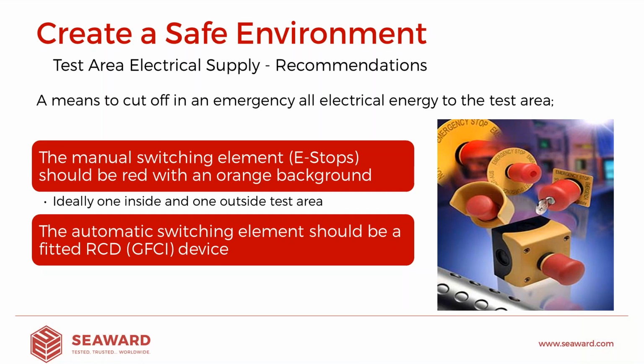What these are designed to do is effectively take the main supply out to the area. Now, from a common sense point of view, we would always advocate installing both one inside the area and one outside of the test area. Effectively, if the operator spots something wrong and needs to cut the power in an emergency, he has the ability to just hit the button and take the supply to the test area out. But similarly, if the worst thing was to happen and the operator was receiving a shock, we want to be able to isolate the area before we put anyone else in harm's way and have them enter the test area. So always make sure there's one outside of the area, so if needs be, that can be disconnected prior to anyone entering the test area.